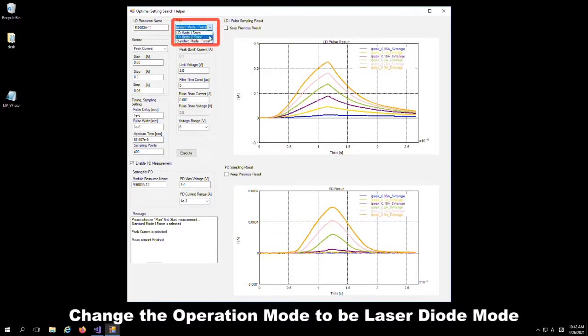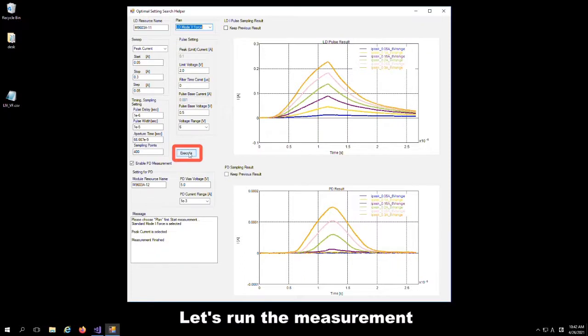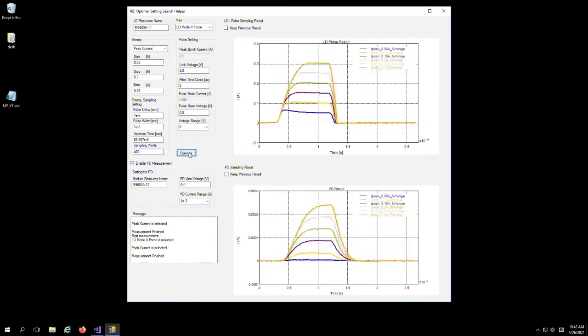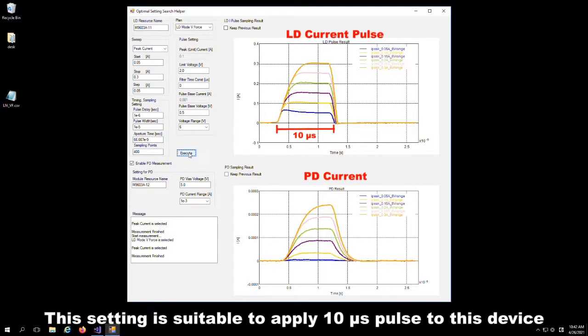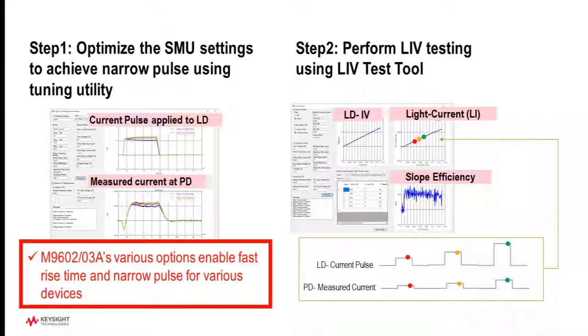Next, let's check the waveform with the laser diode mode. Let's run the measurement. As you can see, the laser diode mode is suitable to apply a 10 microsecond pulse to this device.